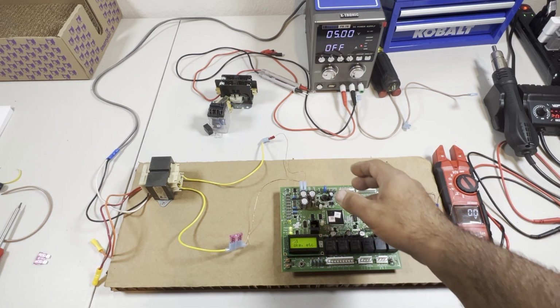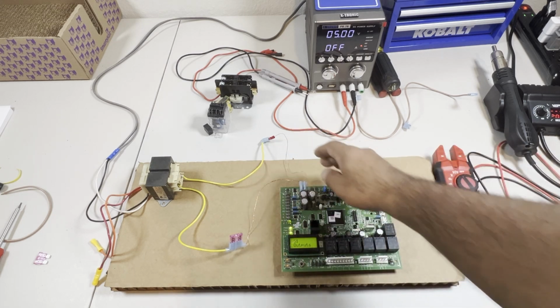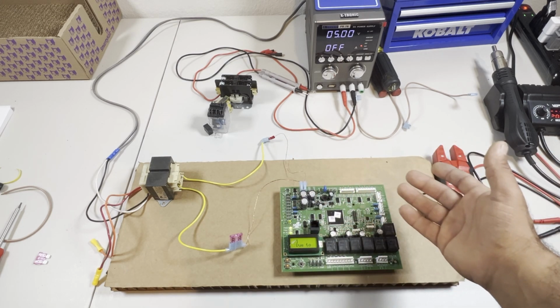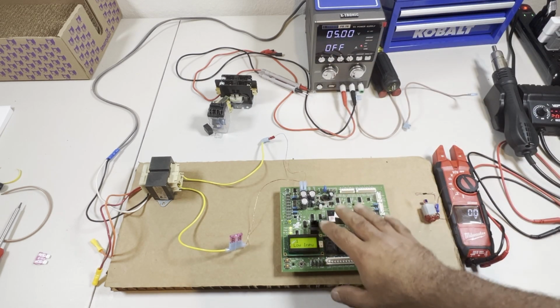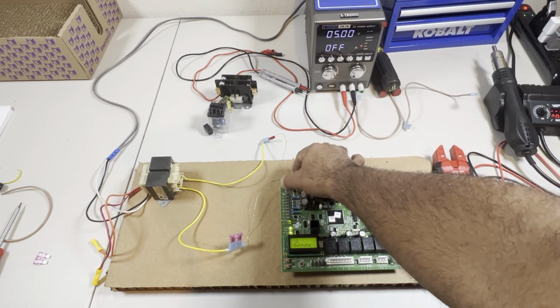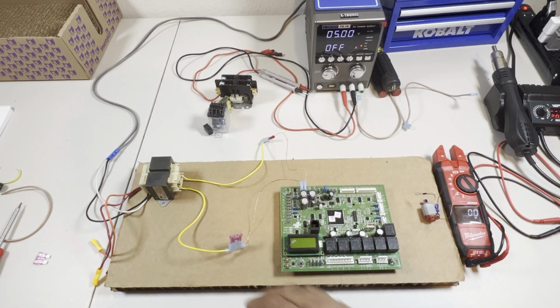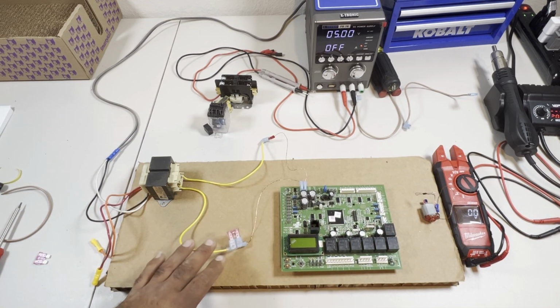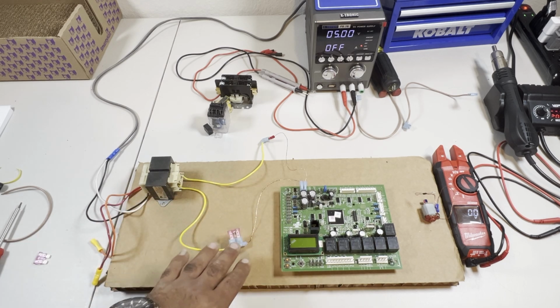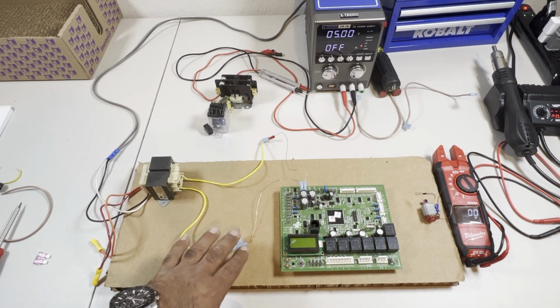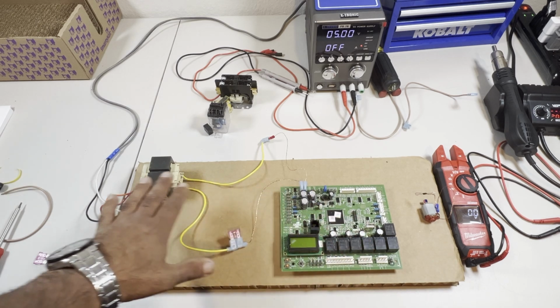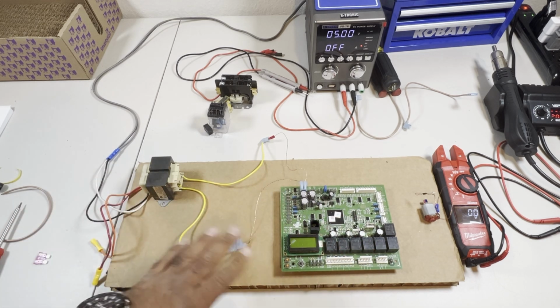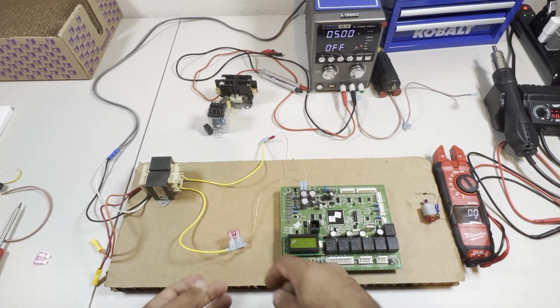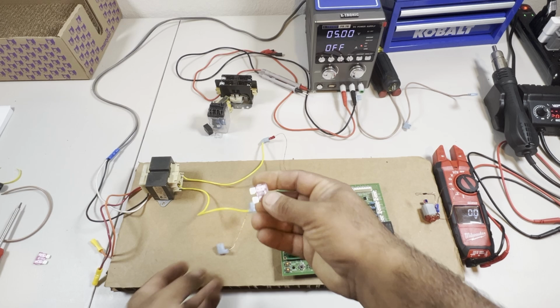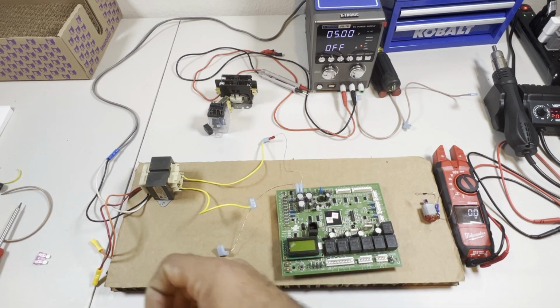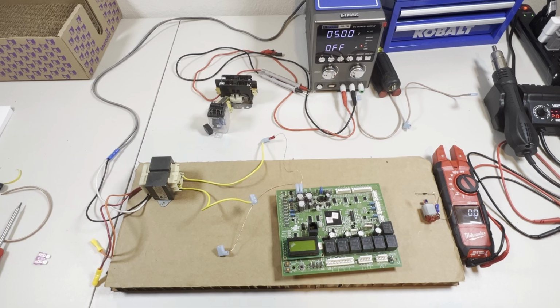Now, what happens when the wires are touching each other, or one of the wires accidentally is touching the ground or rubbing on the side of the cabinet inside the system because the unit is vibrating when it's functioning? This is what happens. That's exactly what the fuse is for. It's the weakest point of your wiring. The fuse is there just to burn itself, sacrifice itself to prevent any kind of damage to your source, wiring, or anything else. The fuse goes out so nothing else burns out. So anytime you see a burnt-out fuse, always check what the cause was, what wire was the problem, which caused that failure.